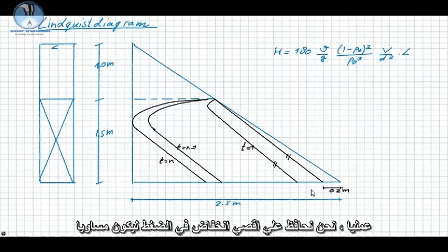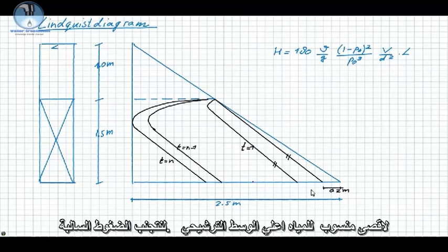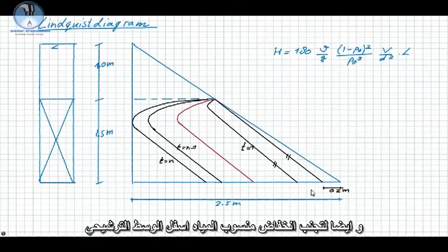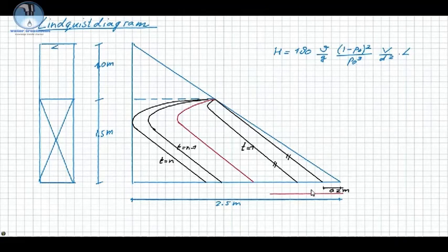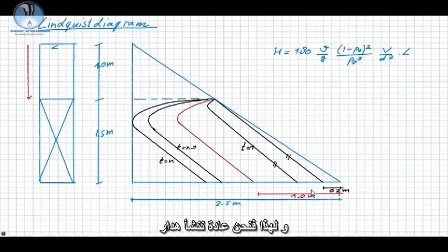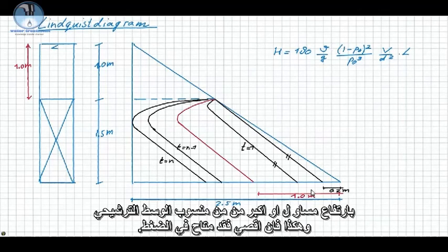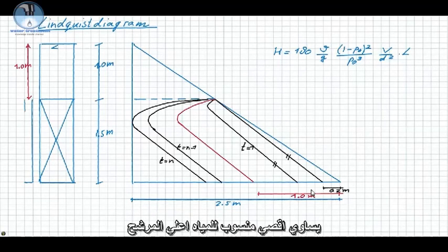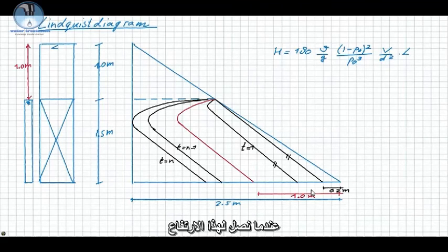In practice, however, we keep the maximum allowable pressure drop equal to the maximum supernatant water level to avoid these negative pressures and also to avoid the water level from dropping below the filter bed. Therefore, we normally construct an overflow downstream of the filter at a height equal to or higher than the top of the filter bed. In this way, the maximum available pressure drop is equal to the maximum supernatant water level. When this level is reached, the filter has to be backwashed.